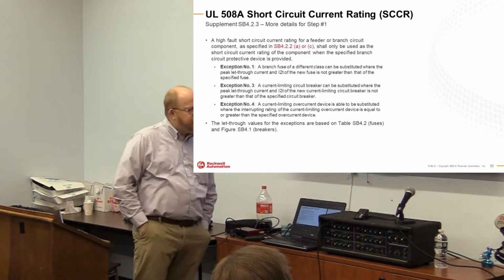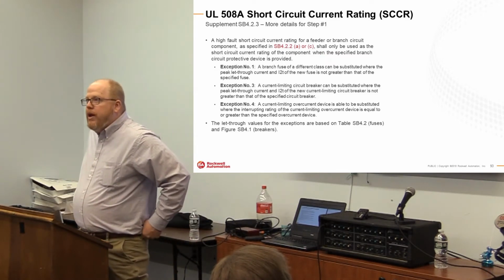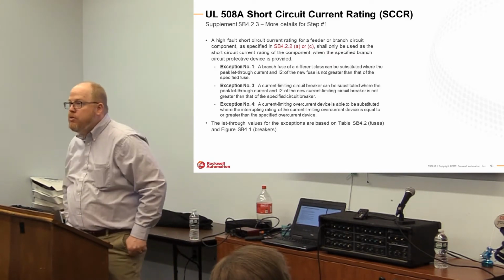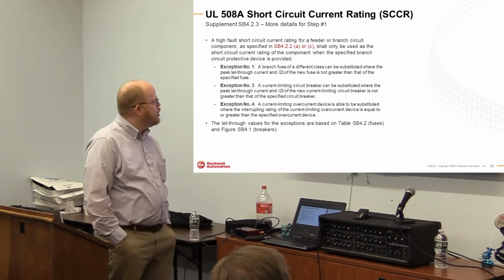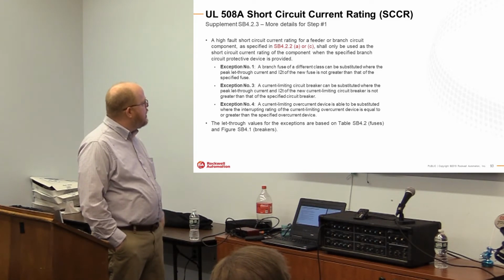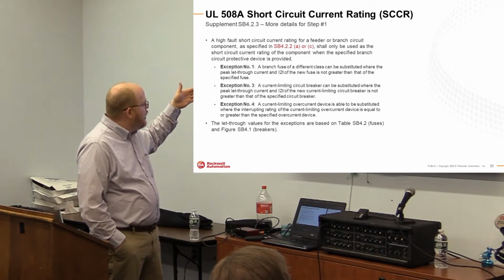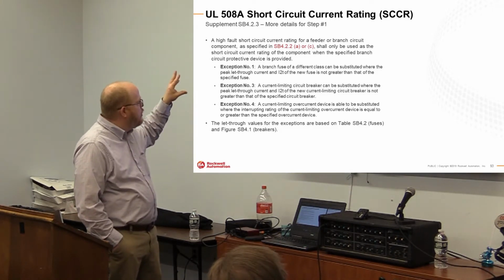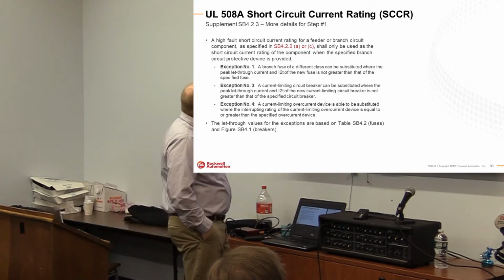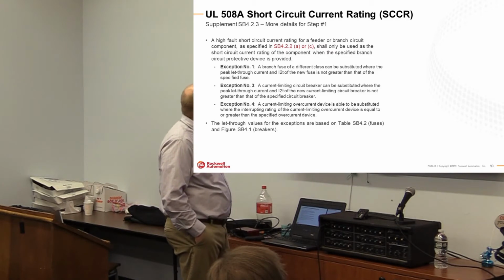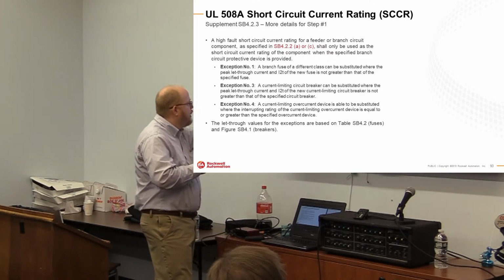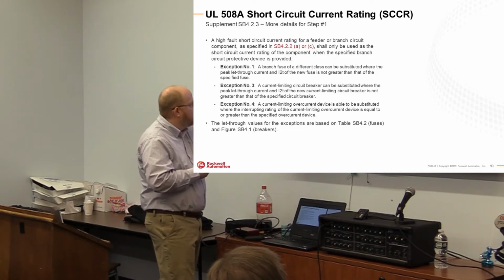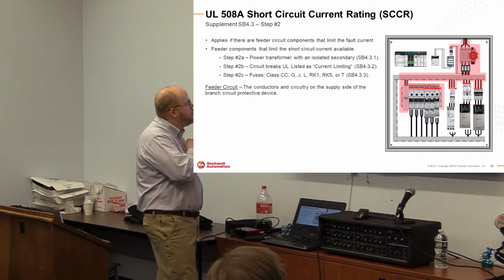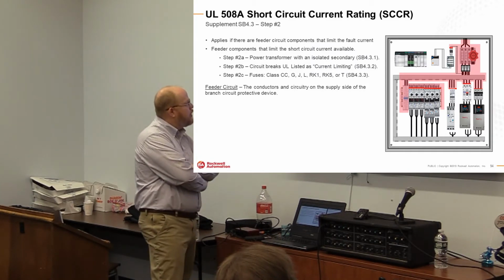Okay, some other things for step 1 that you need to be aware of: the high fault rating of the feeder or branch circuit, where specified, shall only be used in the specified branch or when the protective device is provided. That basically means that you look at the high fault current rating of the branch in conjunction with the protection of the feeder circuit, right? So we can look at the branch circuit as a limiting factor to the available fault of the panel as well, right? And so we also look at let-through currents, which we're going to dive into in a second, for current limiting devices.